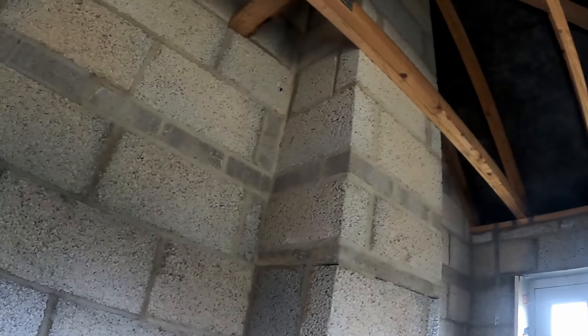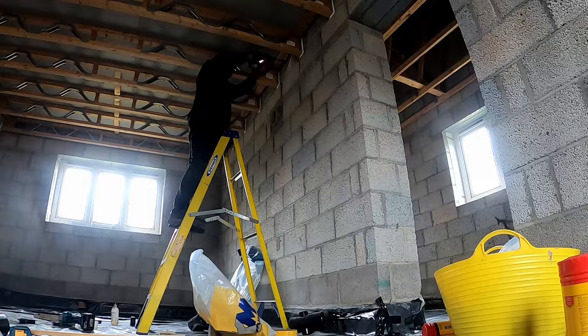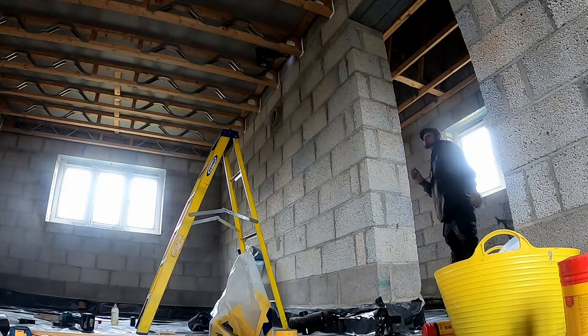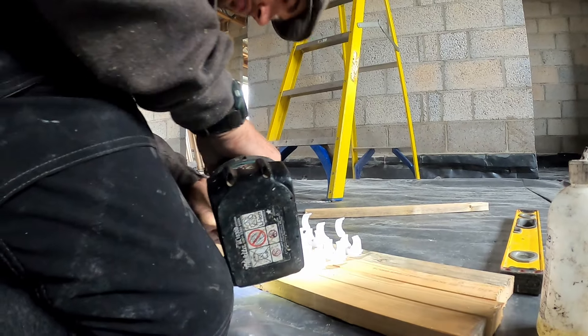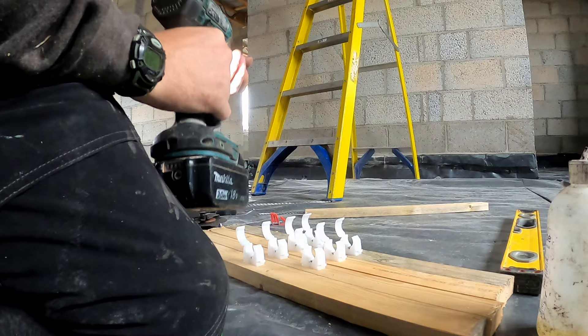Never spotted that one - two different ceiling lights. I'll get a pilot hole for it, that'll be boarded over. I don't know if I can get it in that joist, might have to come through at an angle. And then we might have to put some air taps up here off the boiler. I don't know if they're having a loft hatch in here but we're going to have to put some air taps - it's just going to air lock at the top. The other thing with plastic pipe is you've got to clip it a lot more. If it was copper I'd probably get away with three sets of clips, but with plastic you're probably going to need five.